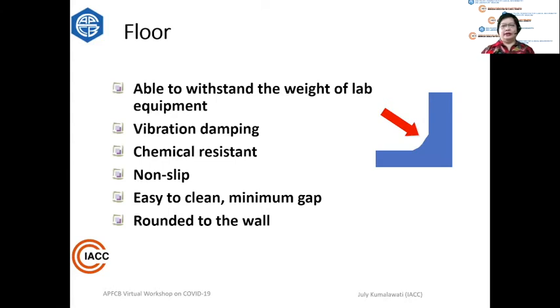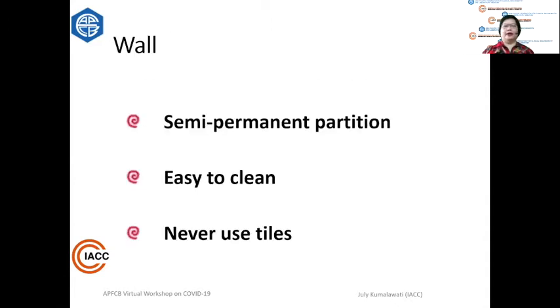Now for detailed physical requirements: the floor must be strong enough, and if possible, it should damp vibrations, be non-slip, easily cleaned with minimum gaps. The angle between the wall and the floor must be rounded so it can be easily cleaned. For walls, it is better to use semi-permanent partitions so that if you need to renovate or change the dimensions of the lab, it can be easily taken off and replaced. It has to be easily cleaned. Please remember, never use tiles on the wall.